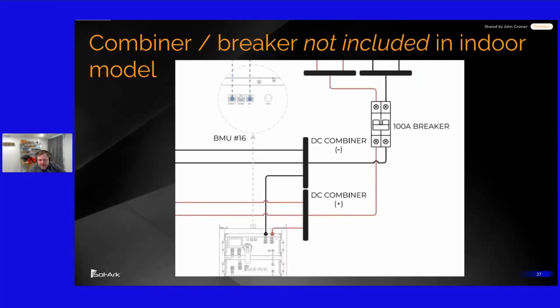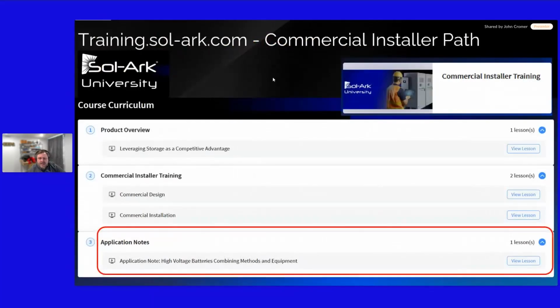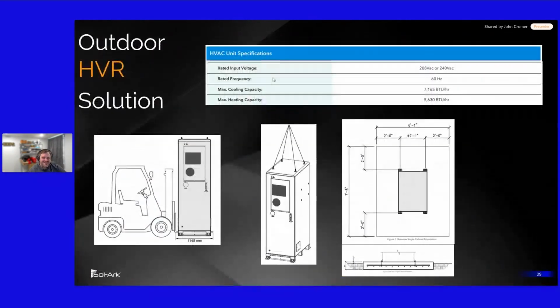But this combiner architecture is not included in the indoor model. We do include combiner architecture in the outdoor model, restricting it to up to 6 inverters, up to 6 battery cabinets per inverter. That's included in this combiner architecture. In our training portal, under our commercial installer pathway, we have a very detailed application note on battery combining that you can follow, or even provide to your inspector if needed.